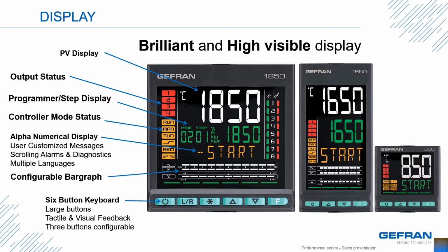That was the 1850 unit. When we move to the 1/8 DIN 1650, you'll see the display is smaller and we lose some information. When I look at the right-hand side of the 1850, you see the 8 in and 8 out lights. This is a feature only in the 1850. The 1650 loses these additional inputs and outputs, not just because of the display, but we also lose some space on the screw terminals on the back of the instrument. The 1650 can still ramp and soak, but we lose some of the display feedback.